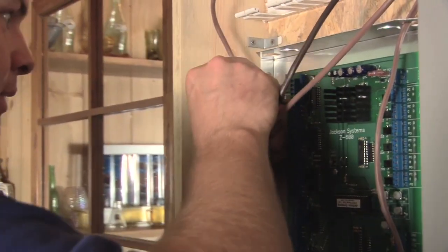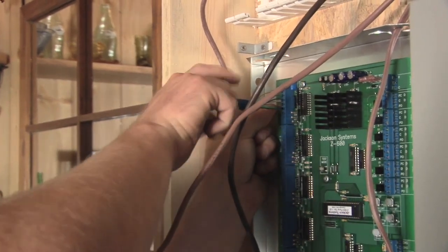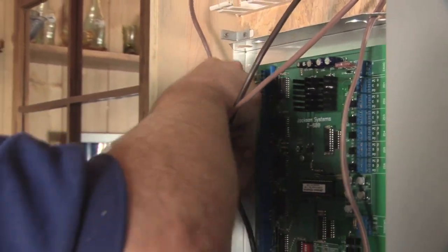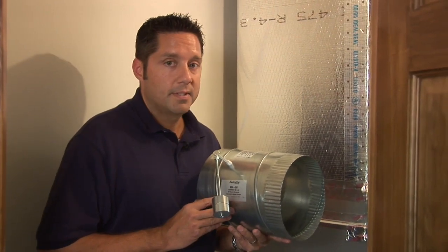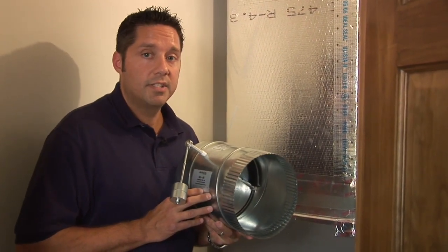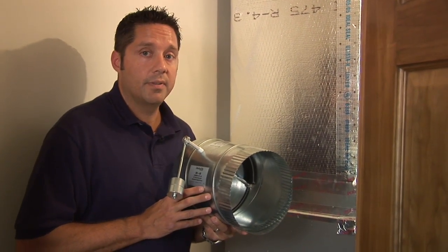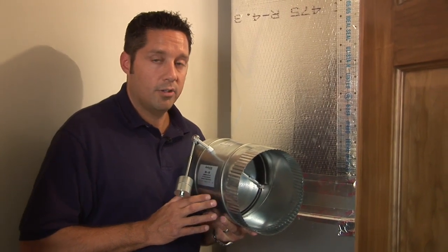As Ryan finishes up wiring the zone control panel, let me explain to you how we're going to install this barometric bypass damper. The bypass damper is designed to help relieve the increased static pressure that happens naturally within the system as zone dampers close off.